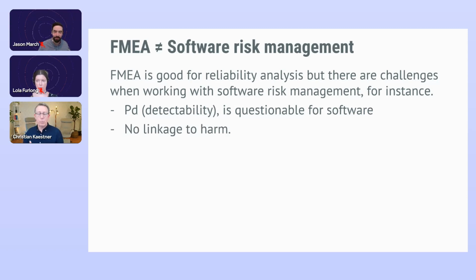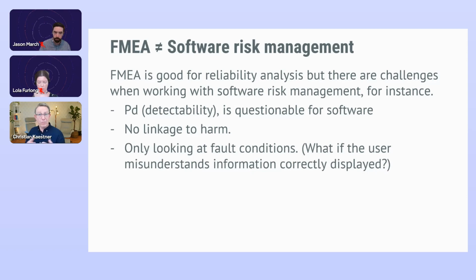There's also another missing part when working with failure mode and effects analysis, and that is there's no linkage to harm. That makes the linkage to system risk management, ISO 14971, missing. So you need to deal with that linkage somewhere to make an FMEA approach equal to software risk management. And lastly, FMEA is all about failures. However, risks may also be a result of functional software. So what if the user misunderstands information that is correctly displayed? Everything is working, but the user is still doing something wrong. That could also be considered a cause. The software is causing trouble for the user, and that could lead to risk. So I think FMEA is limited in scope, still a very useful tool.